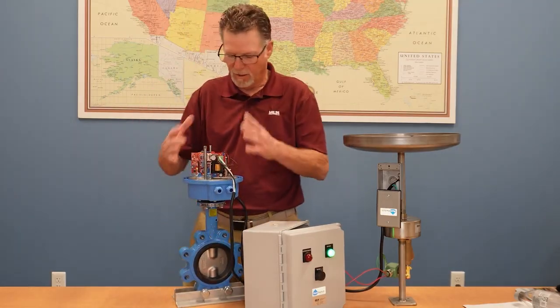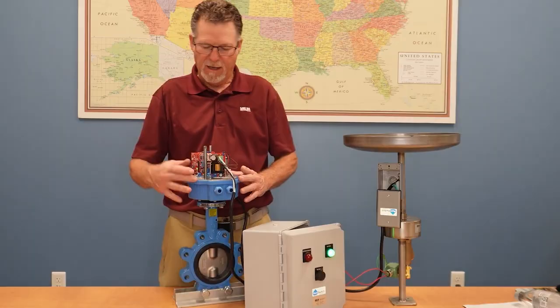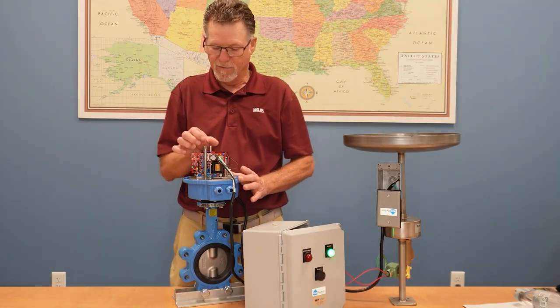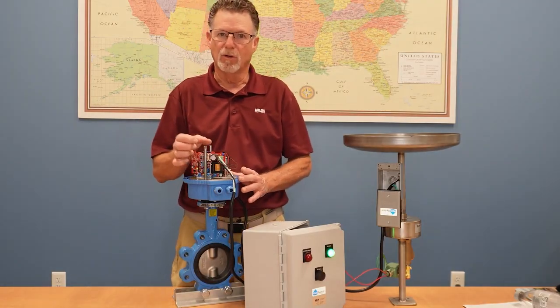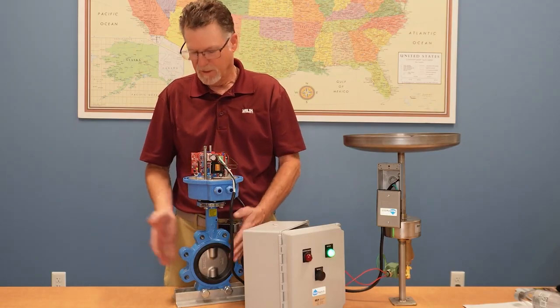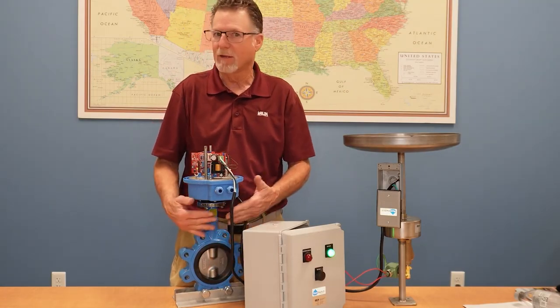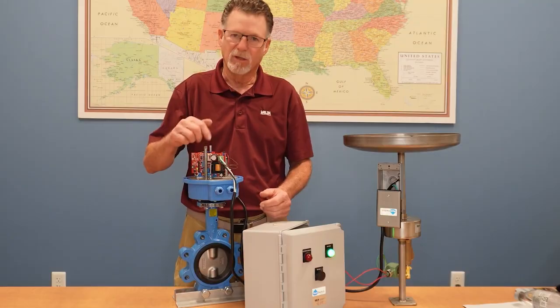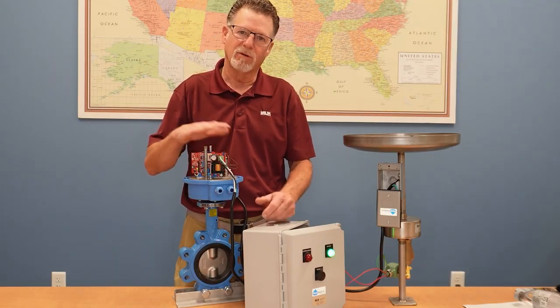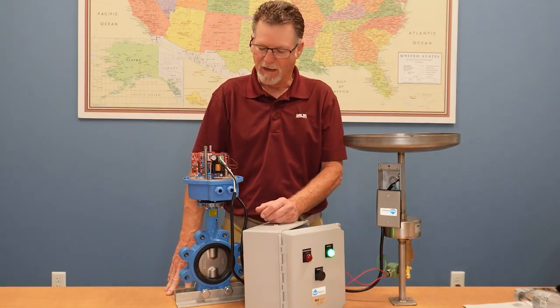There is a lid, the cover on it, and there is an indicator that drives off this shaft and shows open and closed as well. Because when it's installed in the pipe, you can't see its position, so there is an indicator on top of the cover to indicate where the valve's at.